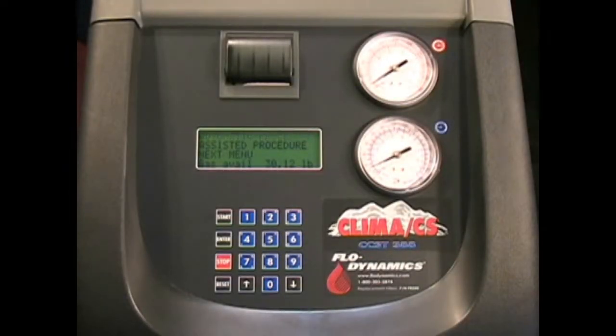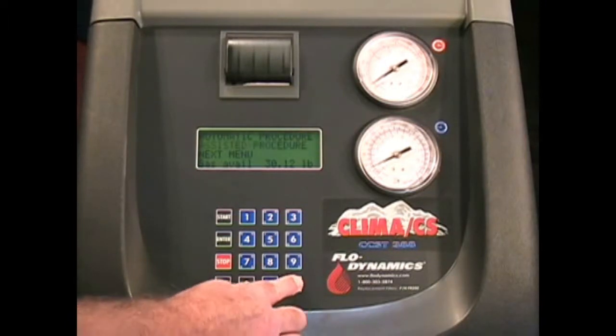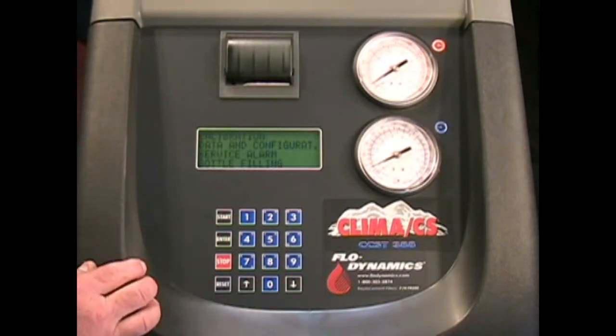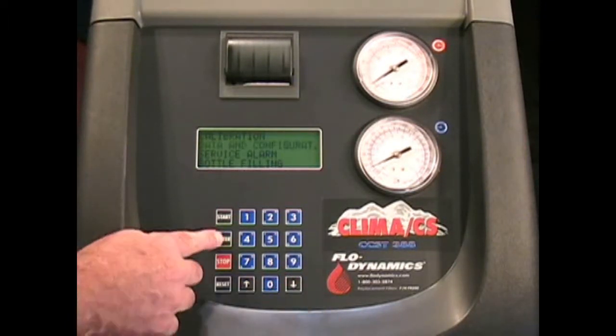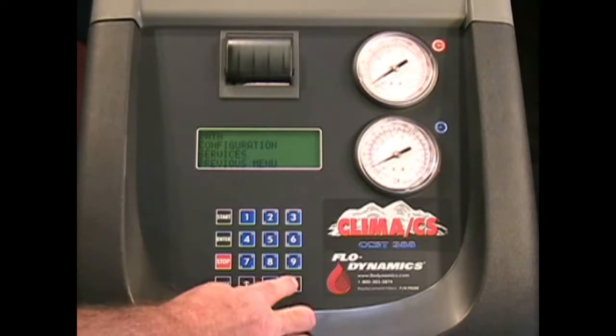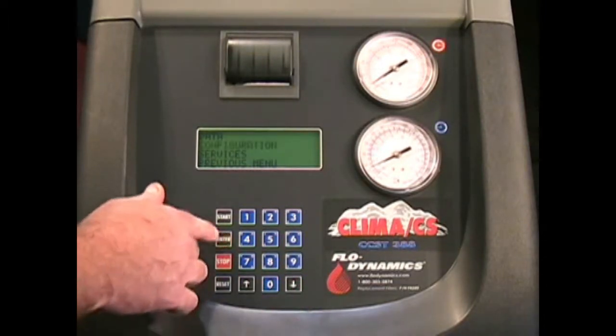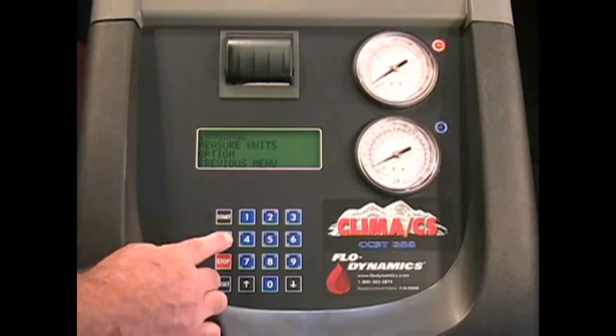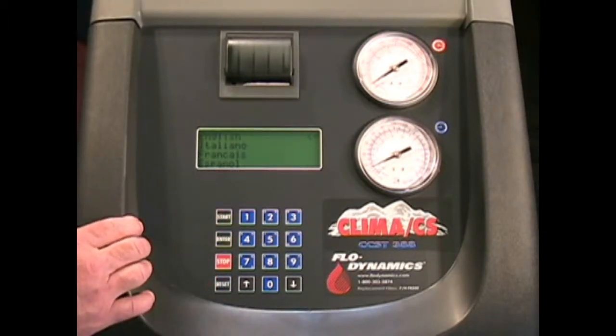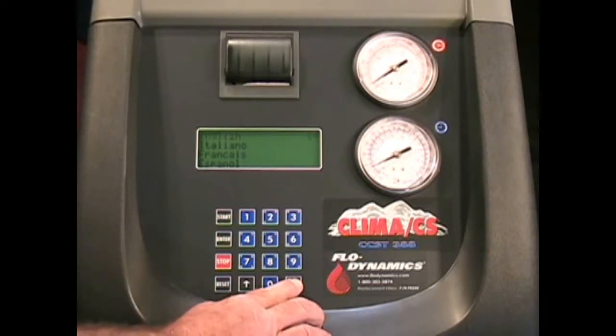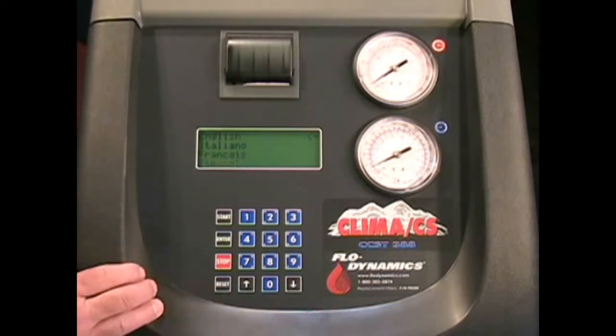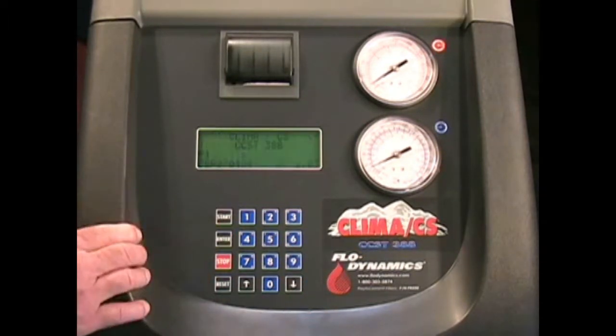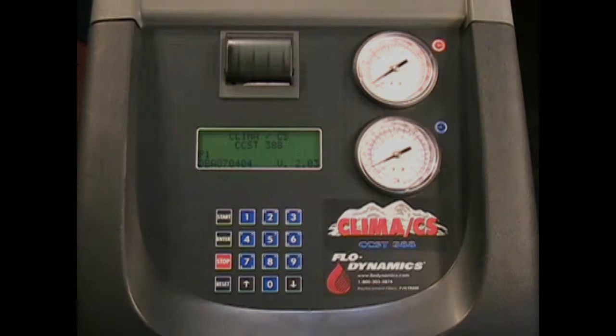Your CCST388 can display in 12 languages and 3 measure units. To change languages, arrow to the Next menu and press Enter. Arrow to Data and Configuration and press Enter. Then arrow to Configuration and press Enter. Press Enter when language is flashing. Arrow to the desired language and press Enter. The unit will restart in the selected language.